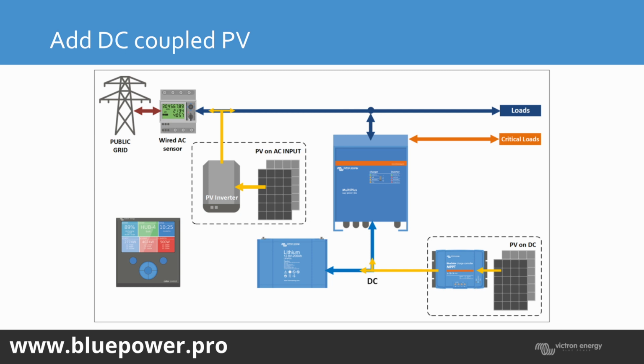because that assists when there's a complete power failure on the system and your battery has drained beyond the disconnect point and ESCOM has failed for an extended period of time. Then your DC solar charger will immediately start charging the battery bank when there's PV available. Whereas the grid-tied inverter is going to require an AC power source to recover and start producing power. So if your inverter is dead or your grid is dead, it's not going to start up to produce power and the system won't recover until the grid source is recovered.